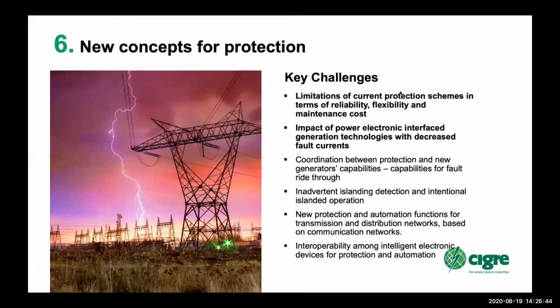The next area, of course, is protection. We have limitations on our current protection schemes, which are fairly set — all the settings on the protection relays are set for a particular fault level, line impedance and load. Now that is changing all the time.